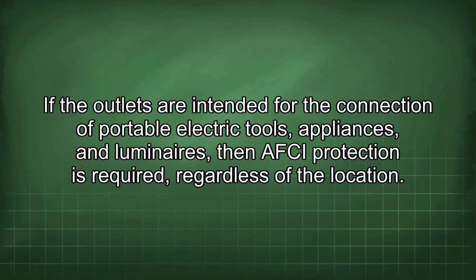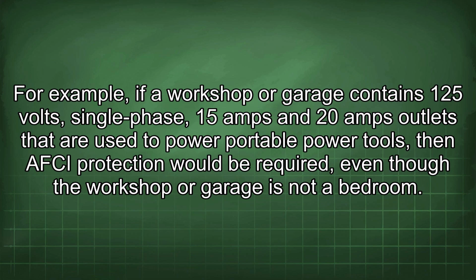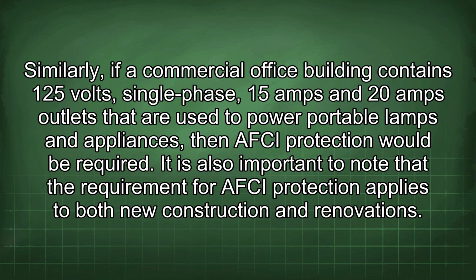If the outlets are intended for the connection of portable electric tools, appliances, and luminaires, then AFCI protection is required, regardless of the location. For example, if a workshop or garage contains 125 volts, single-phase, 15 amps and 20 amps outlets that are used to power portable power tools, then AFCI protection would be required, even though the workshop or garage is not a bedroom. Similarly, if a commercial office building contains 125 volts, single-phase, 15 amps and 20 amps outlets that are used to power portable lamps and appliances, then AFCI protection would be required.